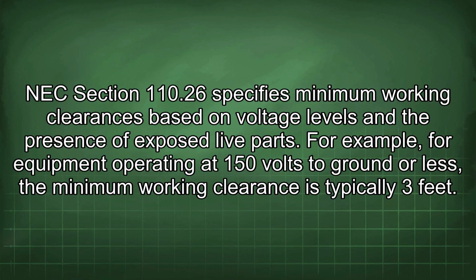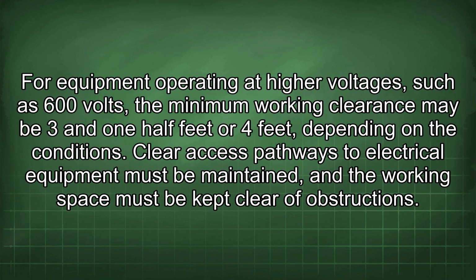For example, for equipment operating at 150 volts to ground or less, the minimum working clearance is typically 3 feet. For equipment operating at higher voltages, such as 600 volts, the minimum working clearance may be 3.5 feet or 4 feet, depending on the conditions. Clear access pathways to electrical equipment must be maintained, and the working space must be kept clear of obstructions.